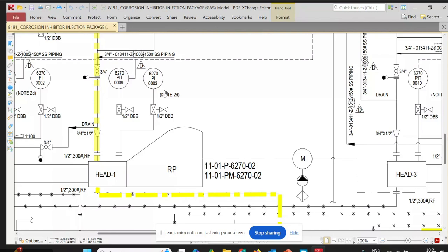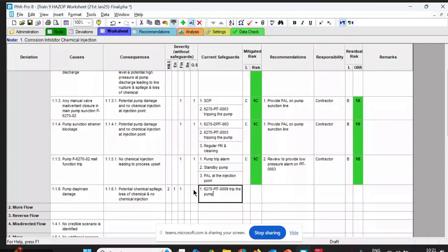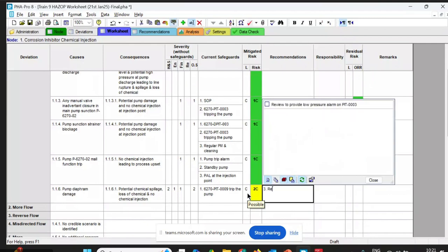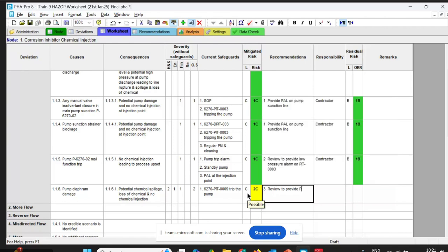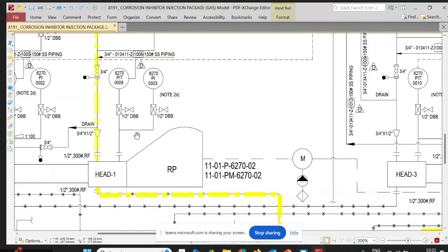And you have got an alarm also? Is this a local PI or is it an alarm? No, that is a local PI. There is no alarm. Okay, so you want to take a recommendation, review to provide? Let us take one recommendation. But here the alarm will be from the same transmitter that triggers the trip. So what is the harm? At least we can know there is some problem before tripping the pump. We can go and trip the pump.